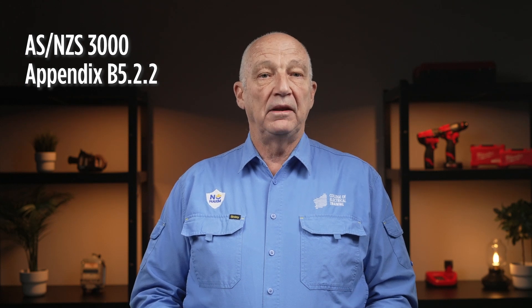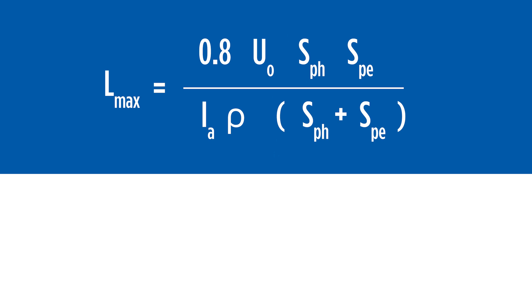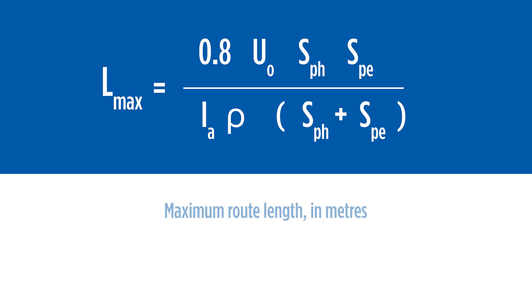One method of verifying the requirements of fault loop impedance is to use the calculation outlined in AS/NZS 3000 Appendix B5.2.2. This calculation will give maximum cable route lengths in metres for selected conductor sizes, conductor material, and circuit breaker instantaneous tripping current.